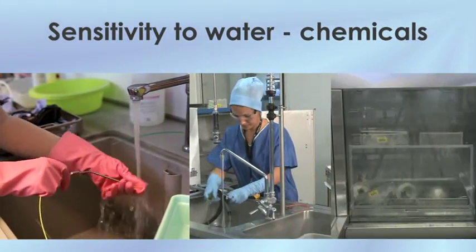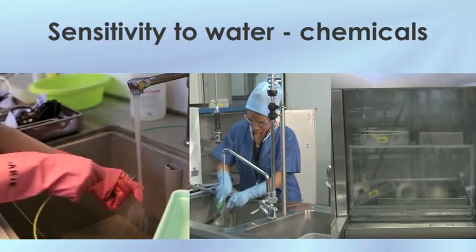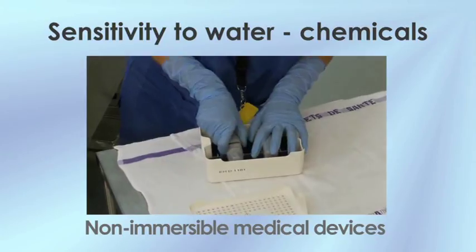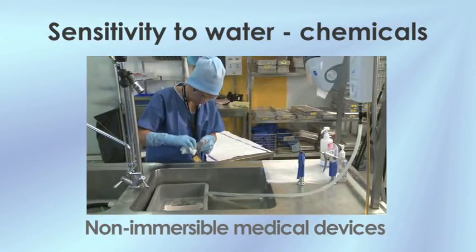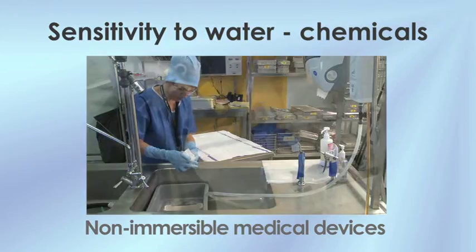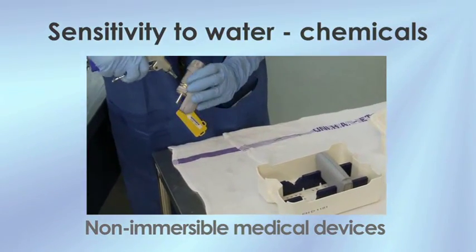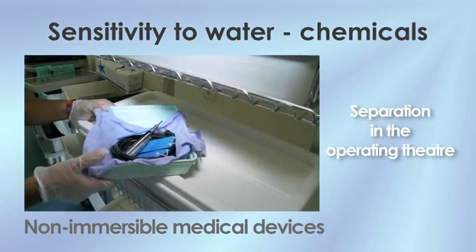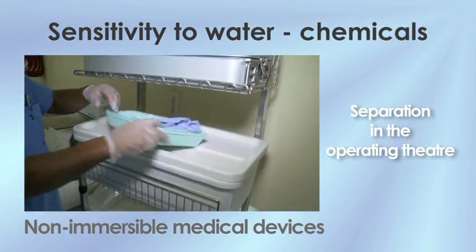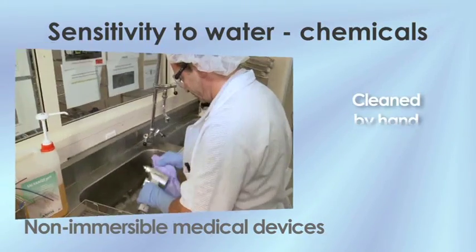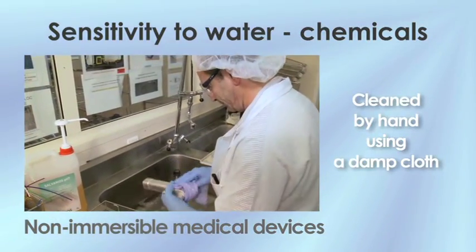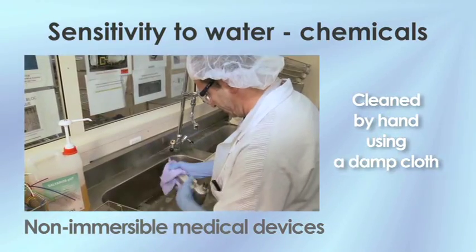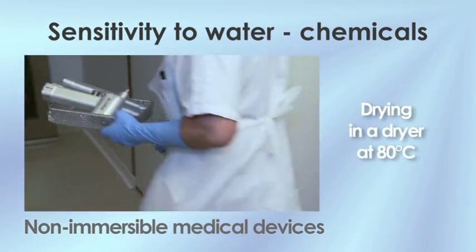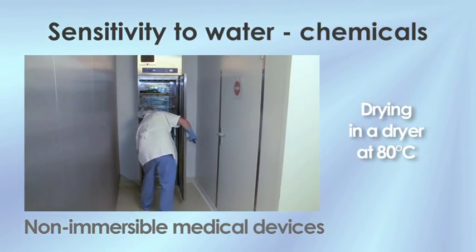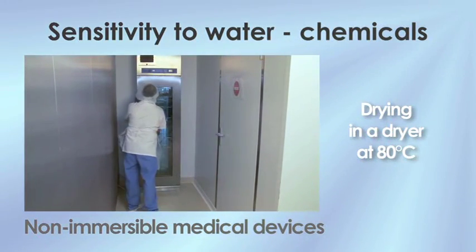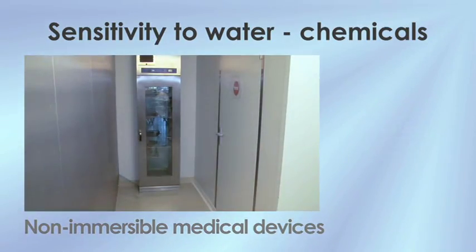Water and detergents are used throughout reprocessing, so special procedures have to be set up to deal with complex MDs that cannot be fully immersed. The parts that cannot be immersed must be handled separately at the beginning of the process in the operating theatre. In the cleaning zone, they are wiped by hand using a damp cloth. To complete cleaning, these complex MDs are placed in a dryer at 80 degrees Celsius, except in the case of incompatibility to heat.